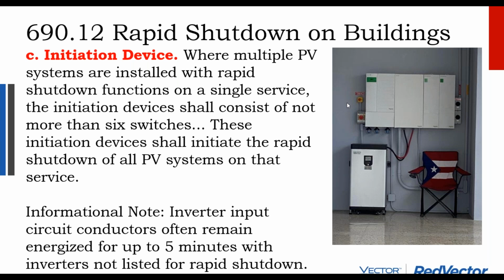So one thing that I think is kind of interesting about this rapid shutdown stuff is it has not yet made its way into the battery conductors, where I think it makes sense for there to be, if you have fire safety, not with backup power, and you could always have true emergency circuits on a non-shutdown circuit. But I fully expect in the future for rapid shutdown philosophy to also be applied to battery systems, but at this time it does not. So your rapid shutdown systems turn the array off up on the rooftop, but not the battery. Maybe you don't need to turn the battery conductors off if they're 5 feet or less or 10 feet or less, but at some point, that probably will get a closer look.